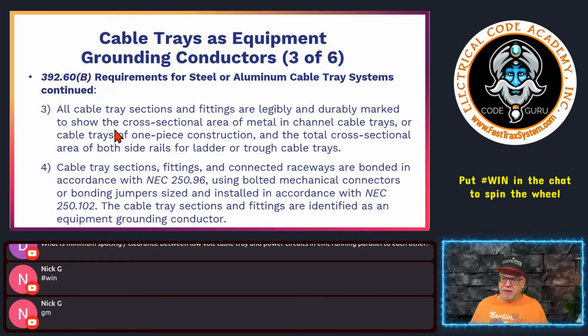It says, okay, more requirements. All the cable tray sections and fittings are legibly and durably marked to show the cross-sectional area of the metal in channel cable trays or cable trays of one-piece construction, and the total cross-sectional area of both side rails for ladder and trough cable trays. All this is done by the manufacturer, but if you don't see these markings anywhere on the rails, on the sides, anything like that, then there's a 99.999% chance that that cable tray is not evaluated or listed for use as an equipment grounding conductor. It's never been evaluated. So don't just look at it and say, it's metal, I'm assuming that it is listed for that, or that it can be used because it is, quote, metal. Don't assume that at all, okay? Look for the markings. You've got to find these markings.